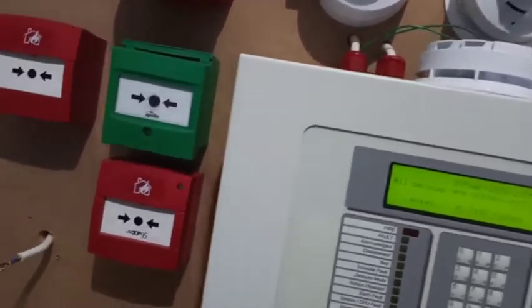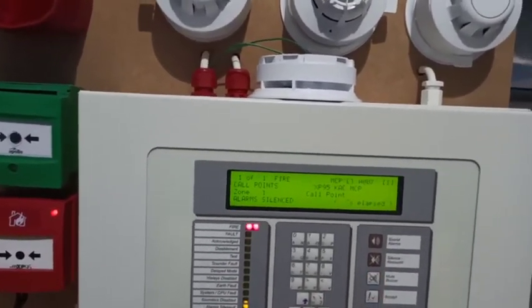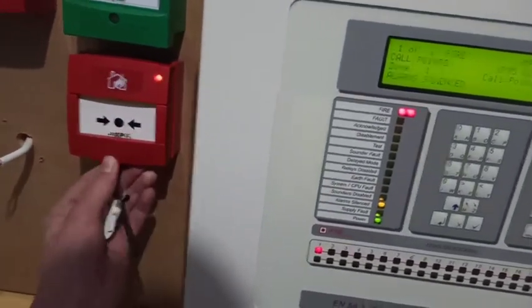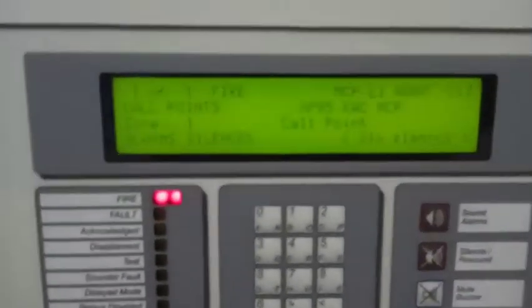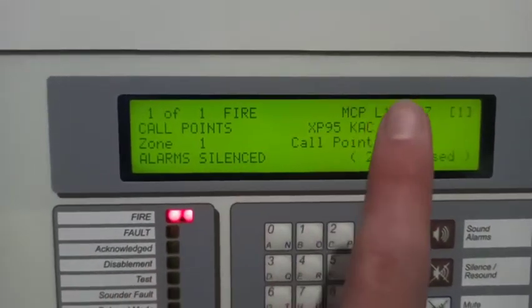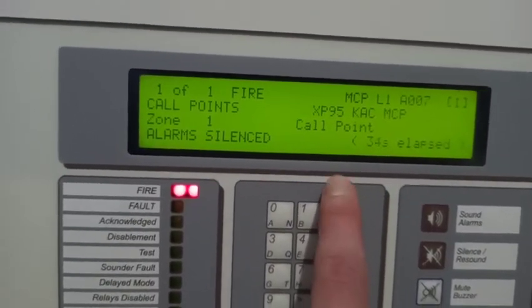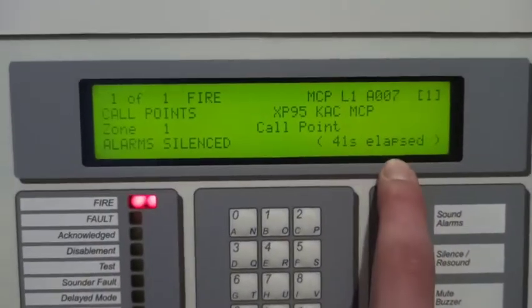We're going to test the zones in order, starting with this call point. Let me reset that — it's quite new so it's a bit awkward to reset. As you can see: one of one fire, address seven, call points is the zone name, XP95 KAC MCP is the device name, zone one call point, alarm silenced, and the time elapsed. The time elapsed feature is quite cool, which I will miss about the Morley.